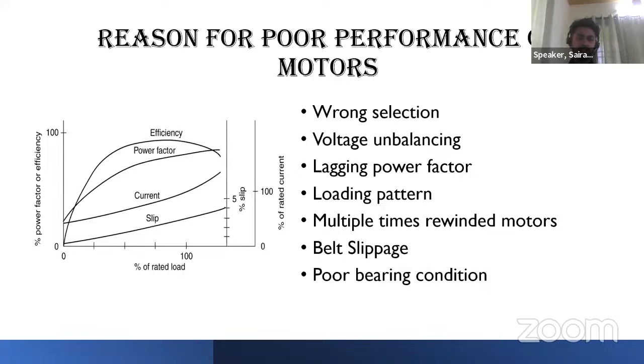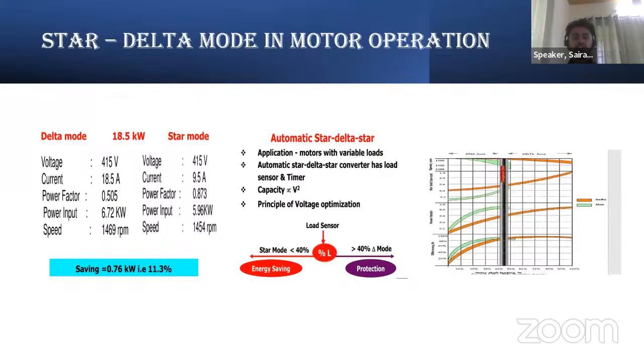If you consider the percentage of the graph here, you could see the slip, current, power factor, and efficiency in relation to the rating of load. If the motor is loaded less than 40%, or else if you could say the motor is underutilized, less than 40%, then you can go for the automatic star delta star converter, which is one of the suggestions that we will be recommending at the industrial site. If we notice the loading percentage of motor as less than 40%, they have wrongly selected the higher capacity motor.